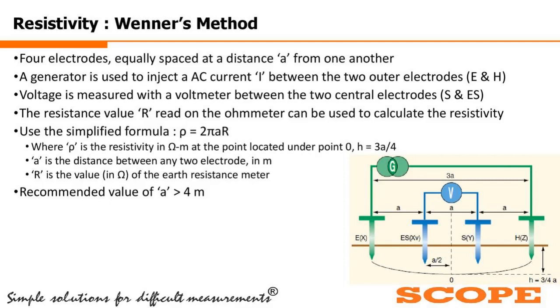And then a voltage generator, or the test kit G, will be used to inject a current I between the 2 outer electrodes, the two green electrodes E and H. And voltage will be measured from the in-between 2 electrodes, that is S and ES, shown in the blue color. The resistance value R displayed on the ohm meter can be used to calculate the resistivity directly.